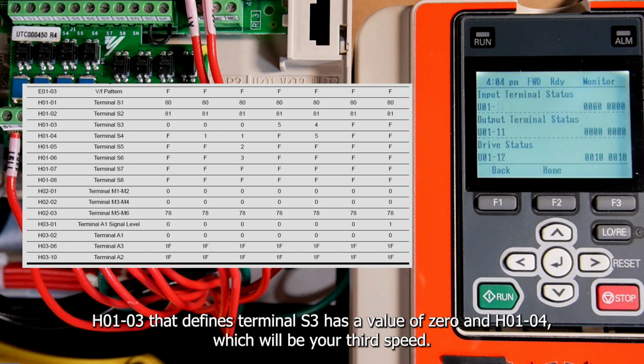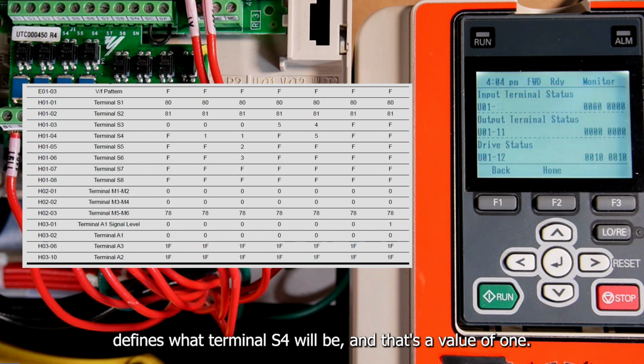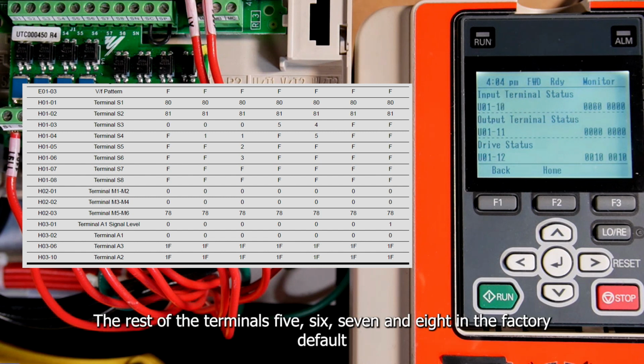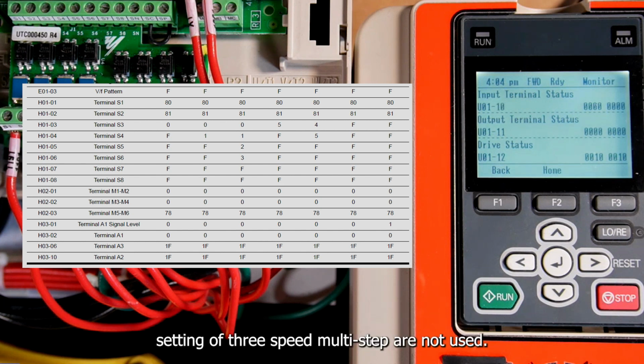H01-03, that defines terminal S3, has a value of 0, and H01-04, which will be your third speed, defines what terminal S4 will be, and that's a value of 1. The rest of the terminals, 5, 6, 7, and 8, in the factory default setting of 3-speed multi-step are not used.